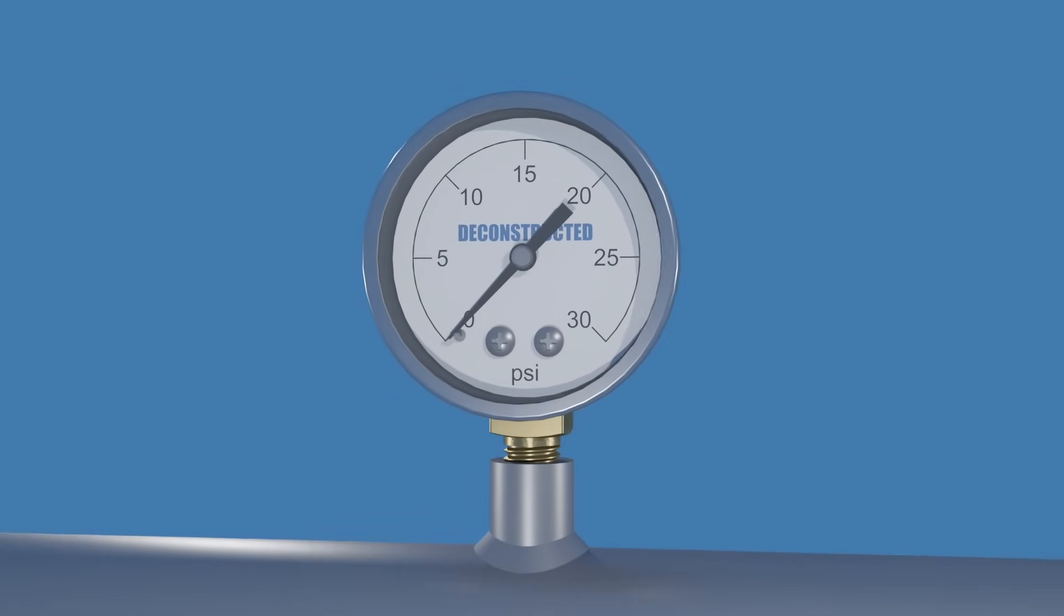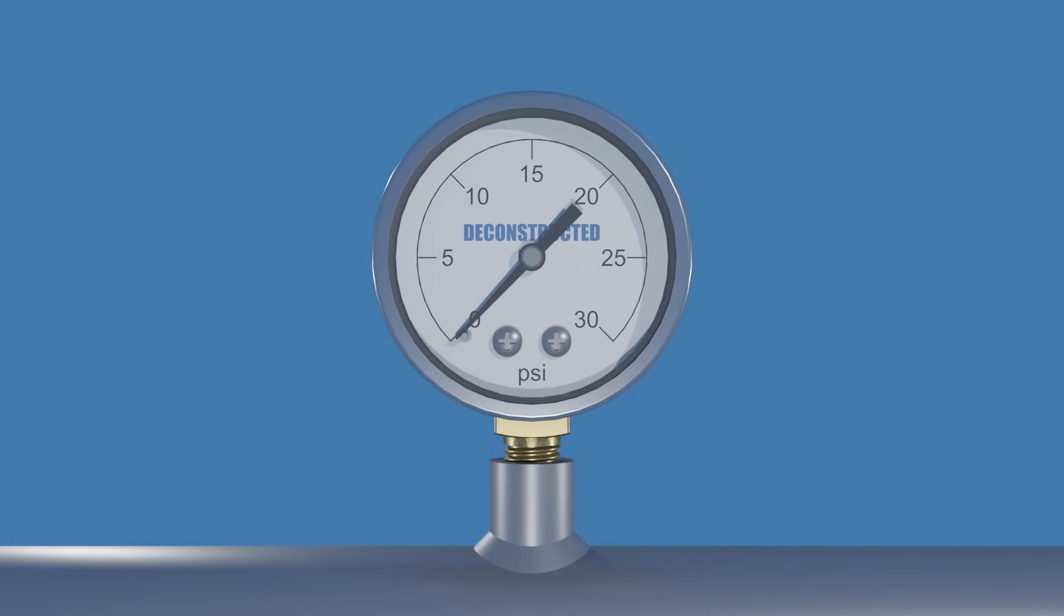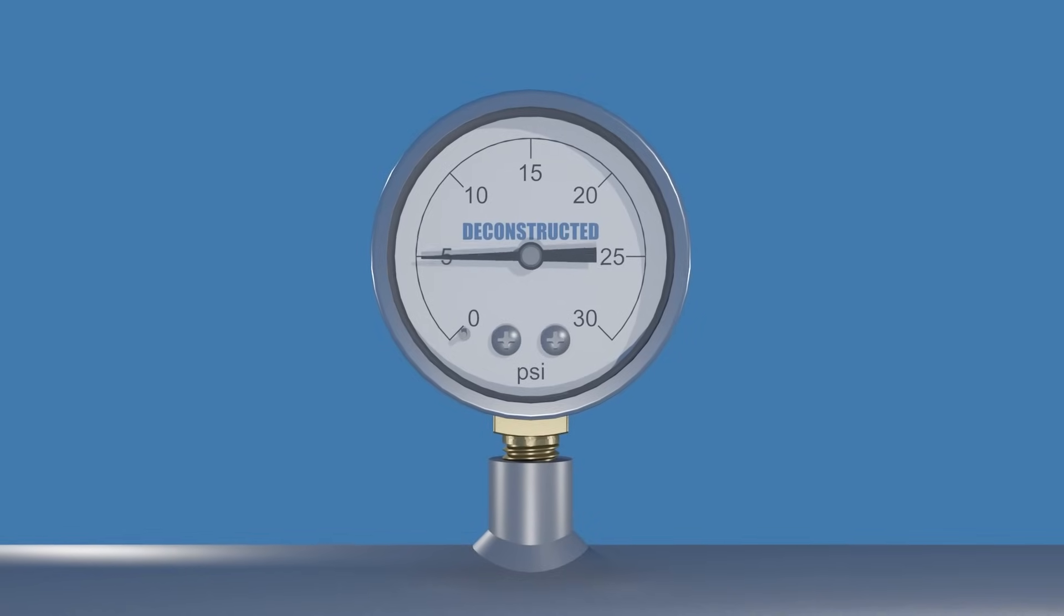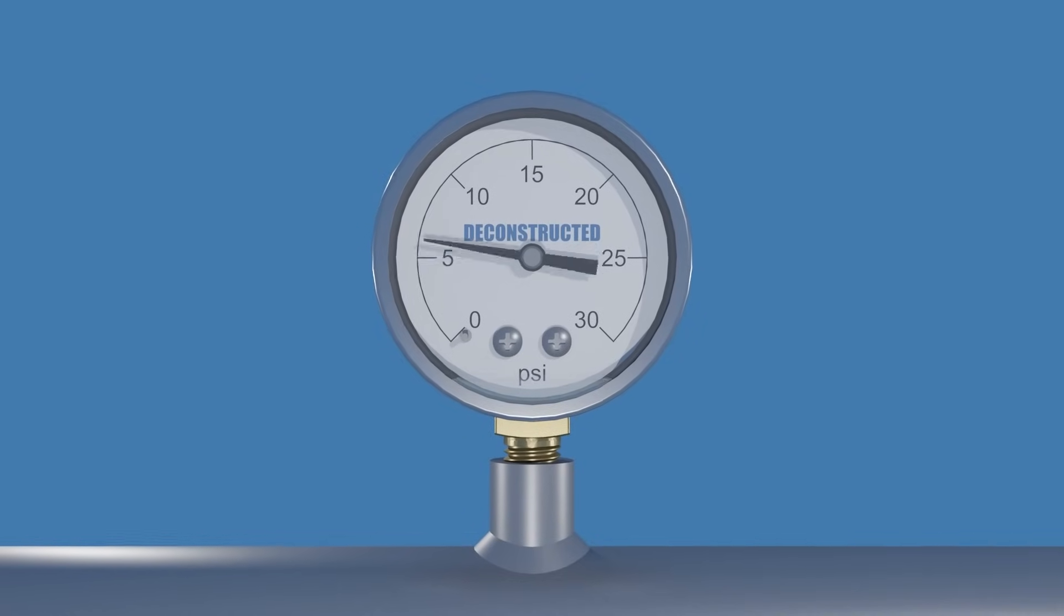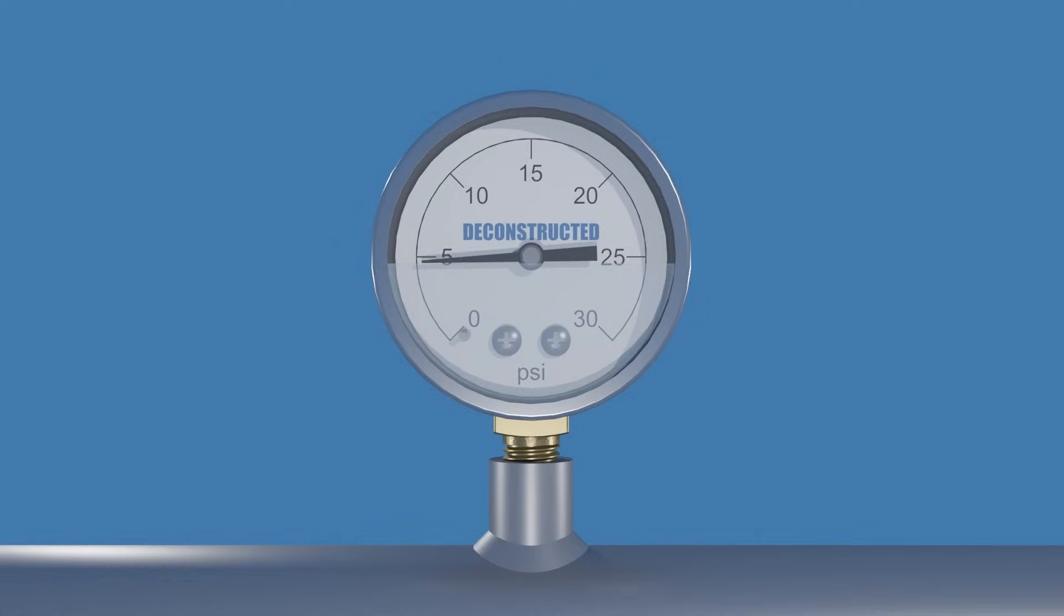Now back to our journey into the mechanics of pressure gauges. Dry pressure gauges are best suited for dry environments, but are sensitive to high physical stress. One of the main advantages of wet gauges is that the liquid dampens vibrations and pressure spikes, preventing them from being transferred to the internal mechanism.